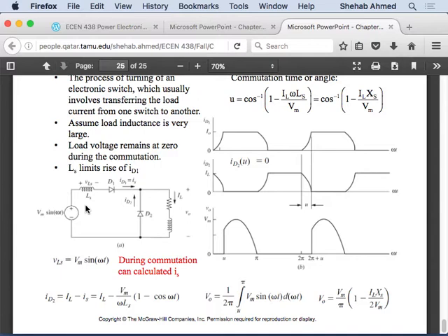You will be given by Kahrama the equivalent impedance: they will tell you the equivalent series impedance until your bus, your input terminals, is so-and-so. So you put that impedance, and then you put a short circuit there and see how much current will flow. And for 59, we do a lot of these calculations. So it's always there. That's why we have to consider it.